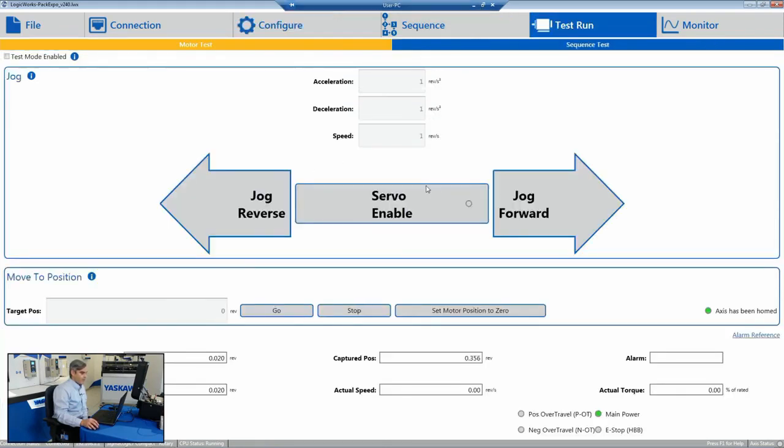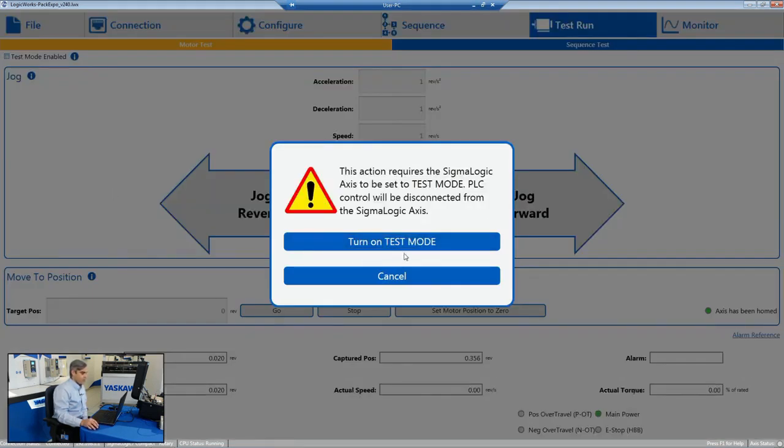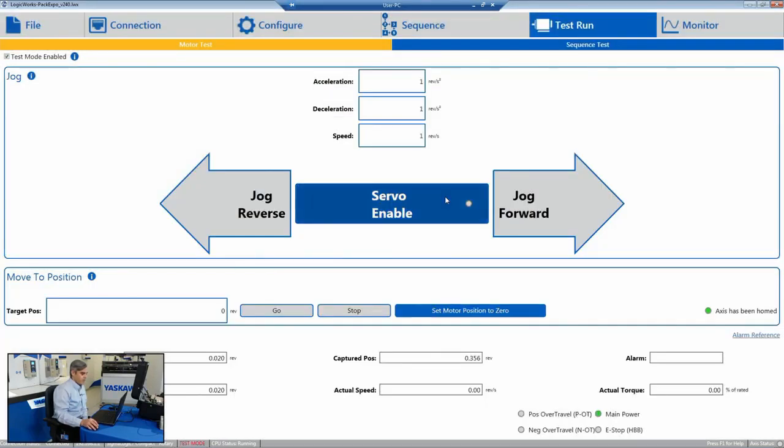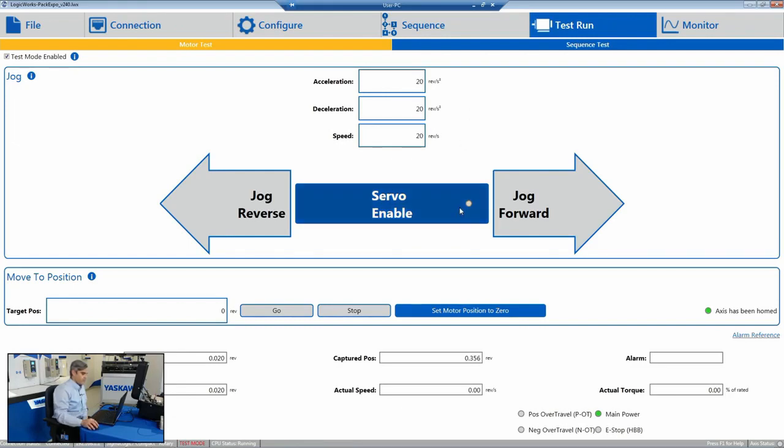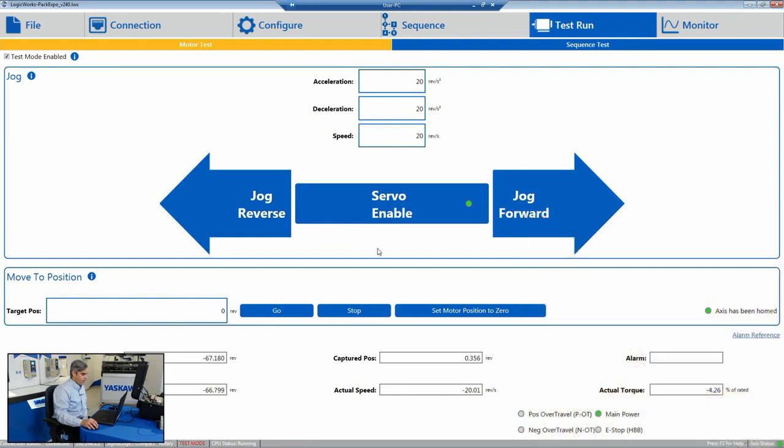And then it also gives an availability of a test run for the Sigma Logic. So before we have it hooked up to an Allen-Bradley PLC, you can control the axis without writing any code. So we confirm that our power wiring, our motor wiring is correct. We can confirm direction. We can confirm scaling, all without writing any code.